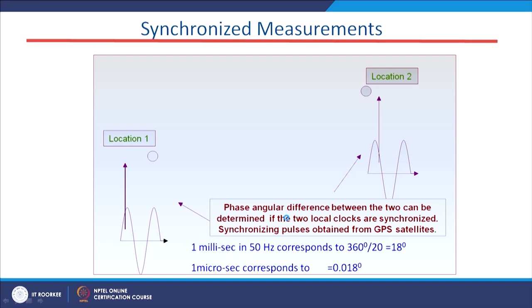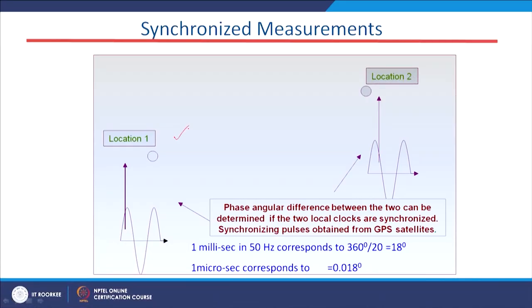Returning to the PMU part — how it measures synchronized phasor voltages and currents. Consider two locations that are apart from each other. At the control center, the voltage phasor V1 from location 1 and V2 from location 2 arrive with the same time stamp. For analyzing these two data sets, the voltage changes must be synchronized; otherwise it is difficult to analyze the two phasors.